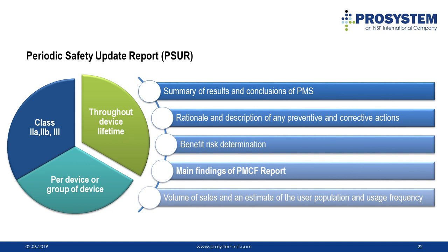We would advise having a clinical expert review and sign off on the PSUR, as this is a key document demonstrating compliance with the regulation and which also must be made public on the EUDAMED database. According to the regulation, we could see that the PMCF findings are one of the inputs for the PSUR. So, theoretically, a PMCF would be required for all these classes of devices.